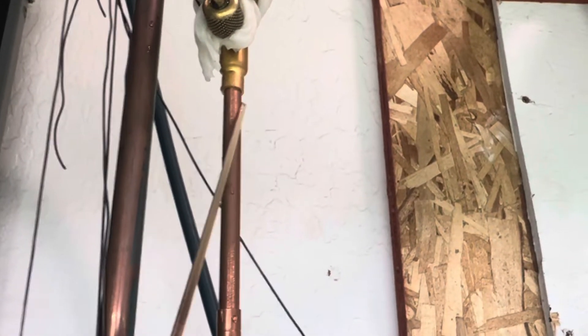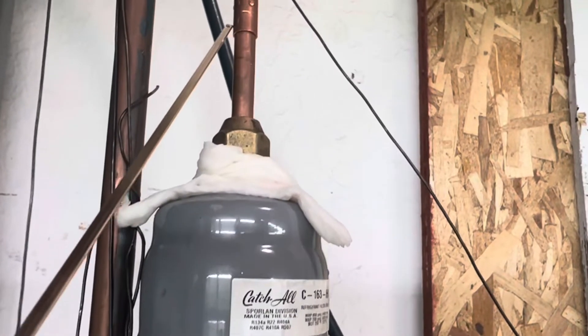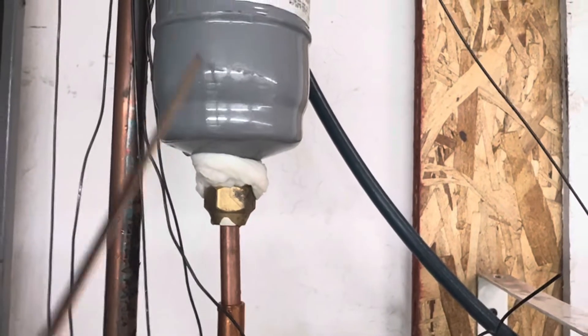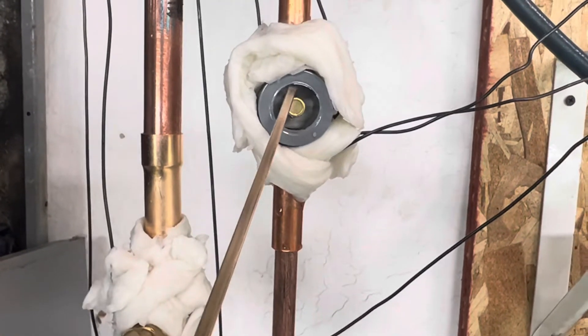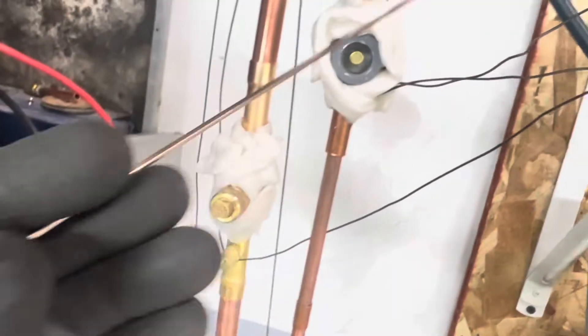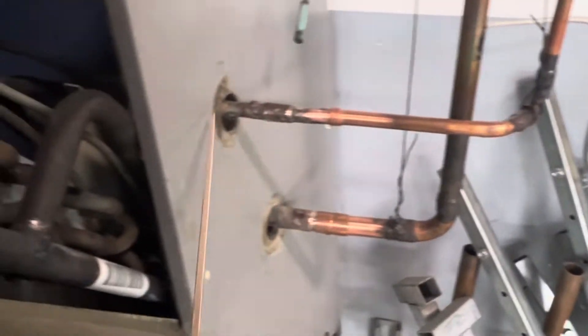That'll make dry, hot nitrogen — the nitrogen is already dry, but it'll be hot. Then I'll be brazing it again here in a second location, making more heat. As this heat and the nitrogen pass by the sight glass, it'll absorb the moisture out of this area. I'll be heating it up here with the 15% silphos and continuing down through as the nitrogen passes through.